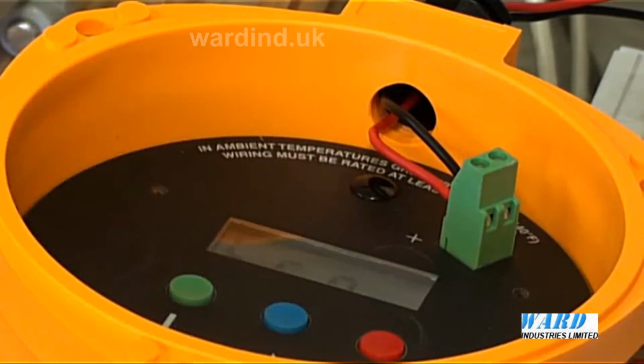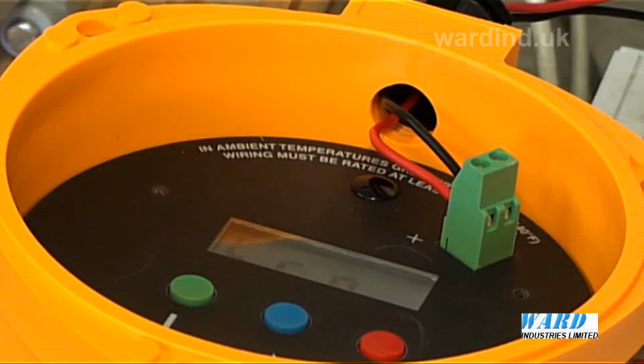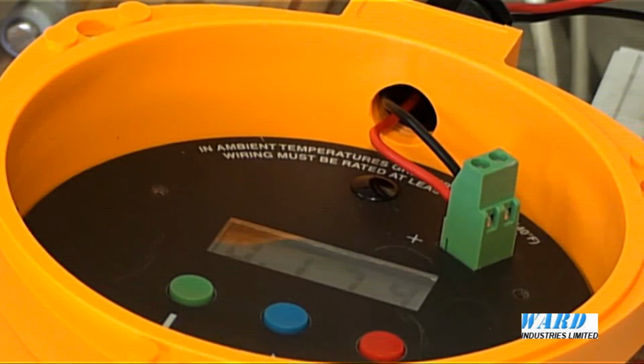The next parameter is Learn. MSP422 has a routine that allows the instrument to learn up to 2 false echoes. These can then be ignored in future operations. If the application is simple and there are no false echoes, as in this example, then press the green button to return the instrument to the normal operating level.